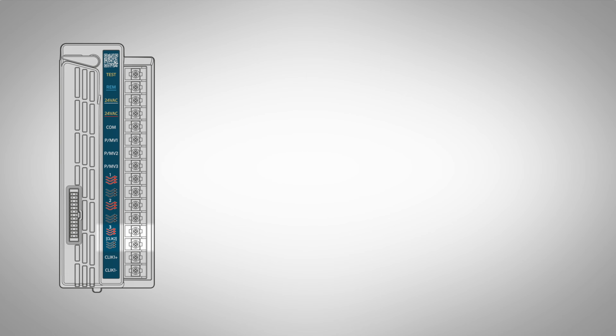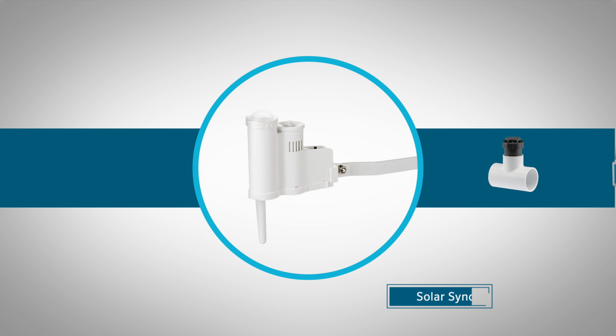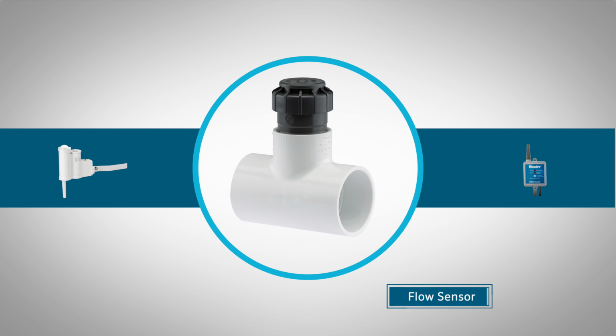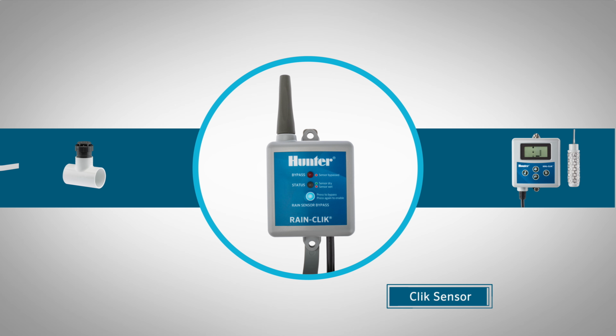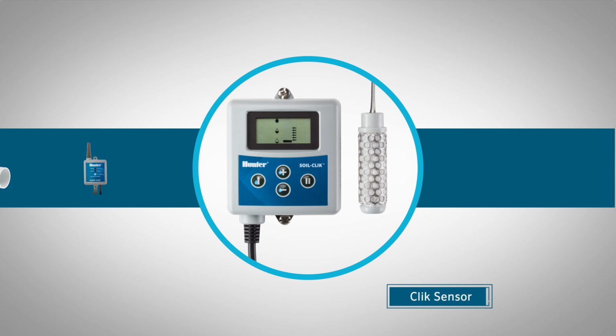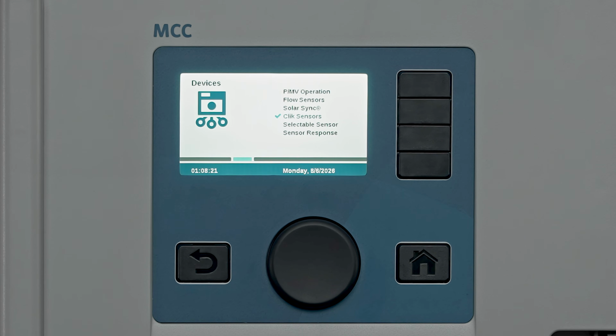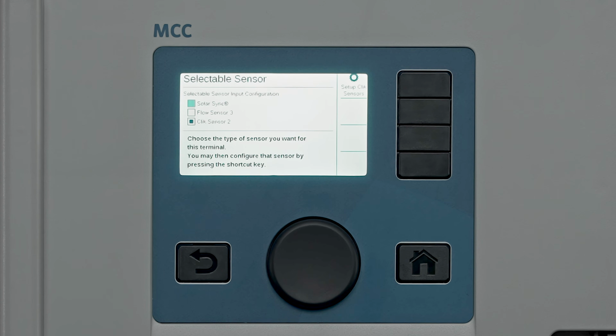A unique feature of the MCC power module is the selectable sensor, which is a single terminal that can be assigned a purpose in the controller display. This can be configured as a solar sync input for automatic climate adjustment, a third flow sensor input, or a second Clik sensor input of any kind. Connect the desired sensor, then use the controller display to go to the device's menu. Choose the selectable sensor, and check the box for the type of sensor you want. After that, the new sensor is available for configuration in the matching devices menus.